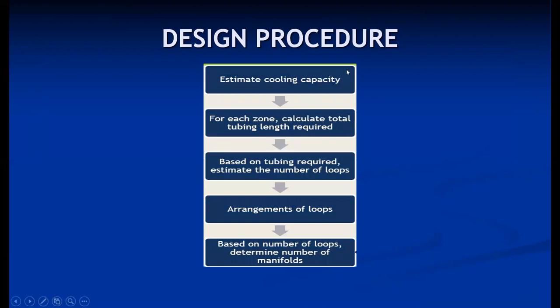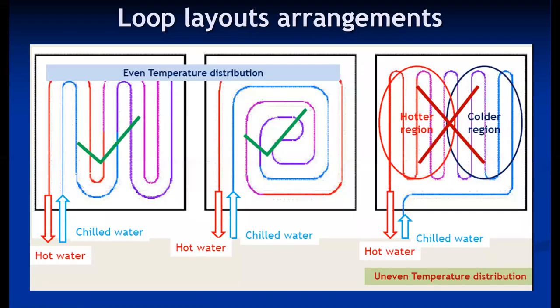Regarding design procedures, for the radiant cooling system: first the cooling capacity is estimated for each zone; then the total tubing length required to meet that cooling capacity is calculated; based on the tubing requirement, the number of loops is estimated; then the arrangement of loops is determined; and finally, based on the number of loops, the number of manifolds required is determined.